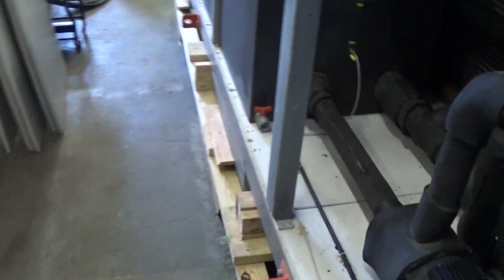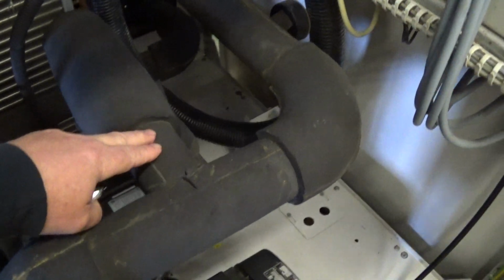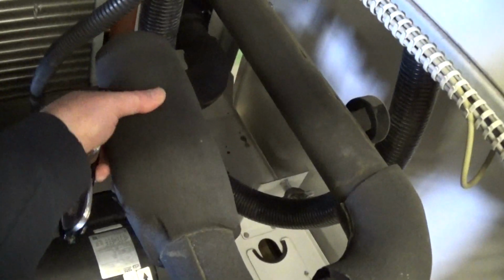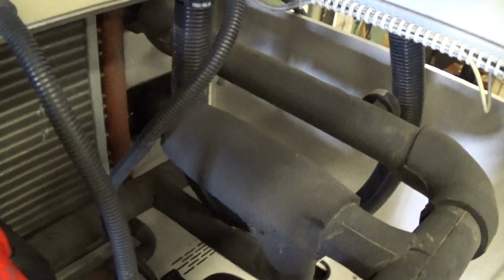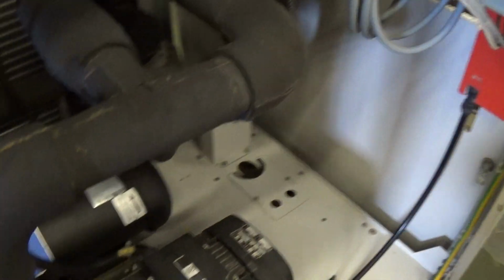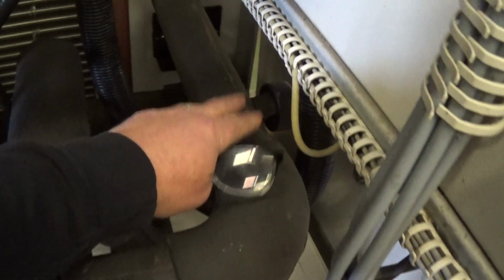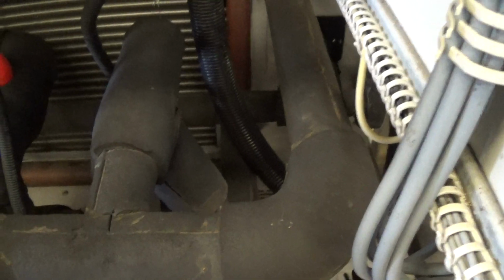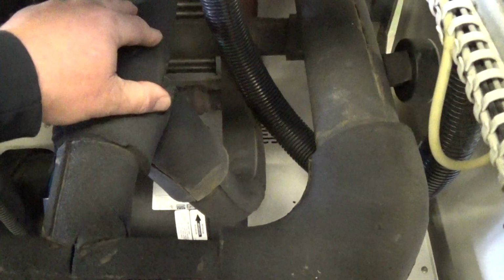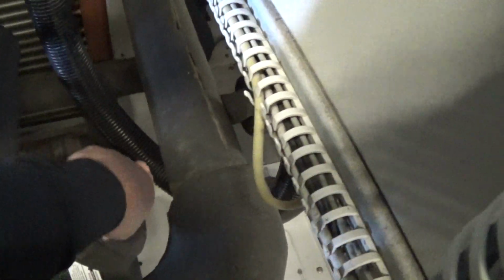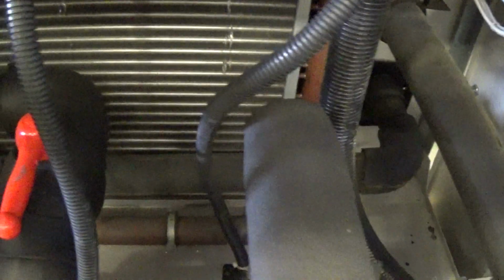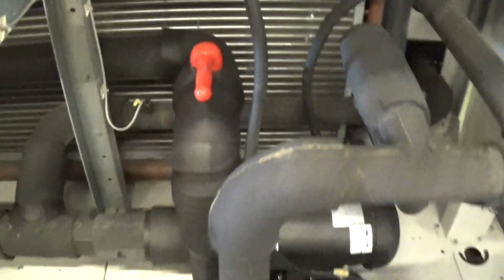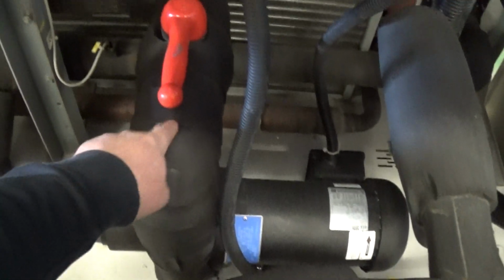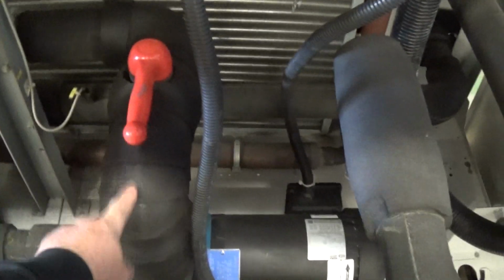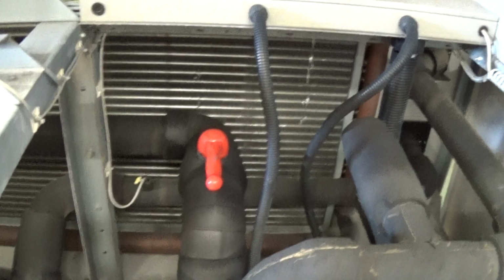The chiller has its own, what the Europeans call a safety valve, which is a valve behind this insulation here, which is effectively a safety bypass valve. So if you were to deadhead the flow out at your process machines, this spring-loaded valve here behind this insulation would get activated, and you still get some flow coming back to the return line, coming back to the chiller. Under normal operating conditions, and we measured the amps, this valve here, which is for service, which again is the chiller loop, you can leave that wide open. You should not have to throttle that down from what we can see.